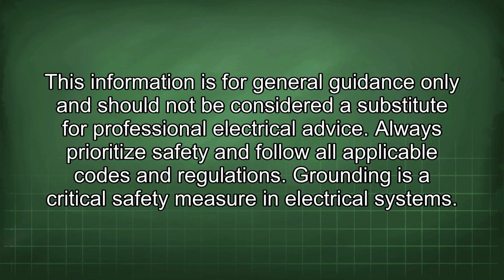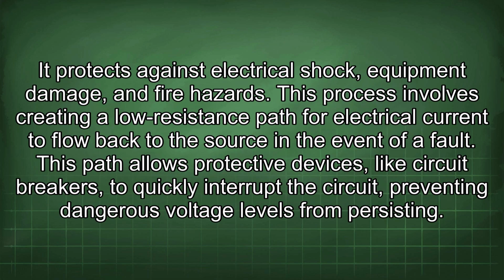Grounding is a critical safety measure in electrical systems. It protects against electrical shock, equipment damage, and fire hazards. This process involves creating a low resistance path for electrical current to flow back to the source in the event of a fault. This path allows protective devices, like circuit breakers, to quickly interrupt the circuit, preventing dangerous voltage levels from persisting.